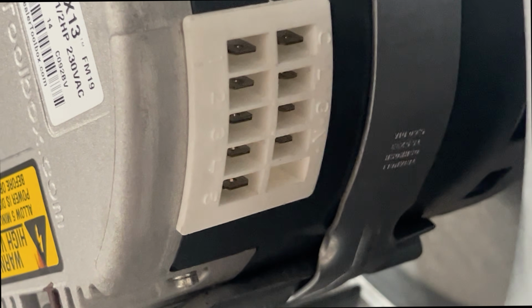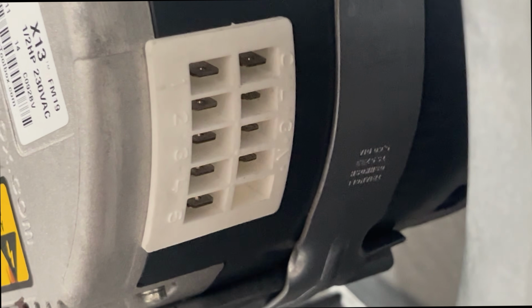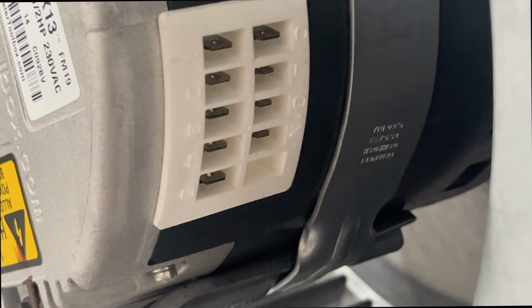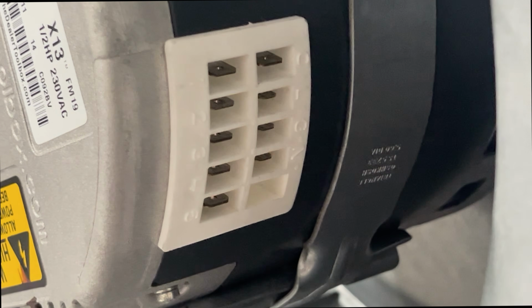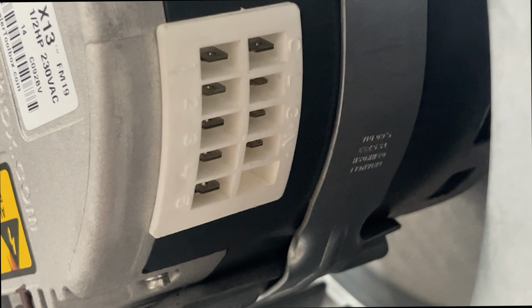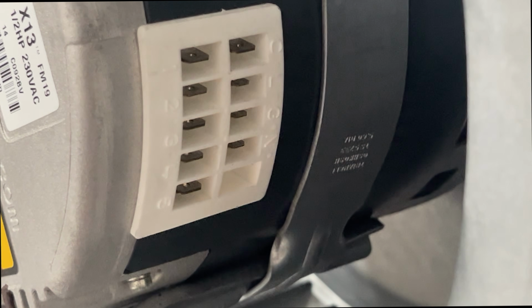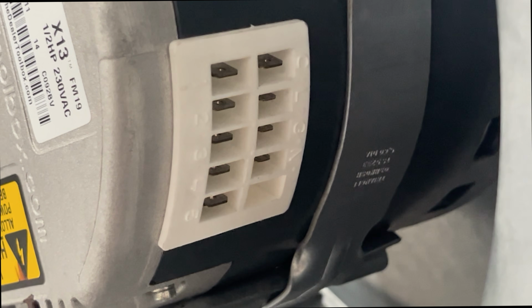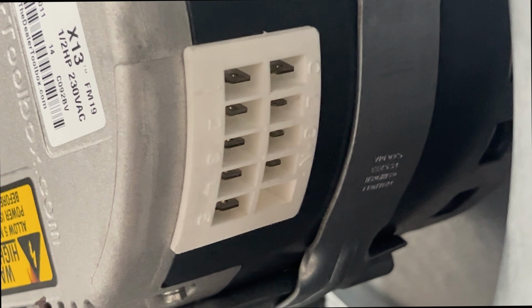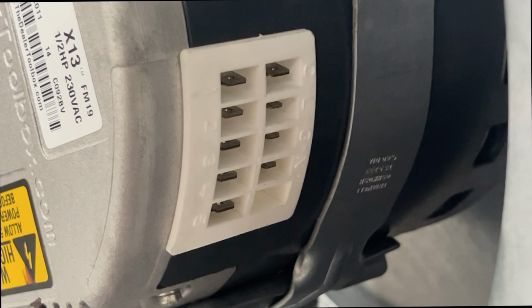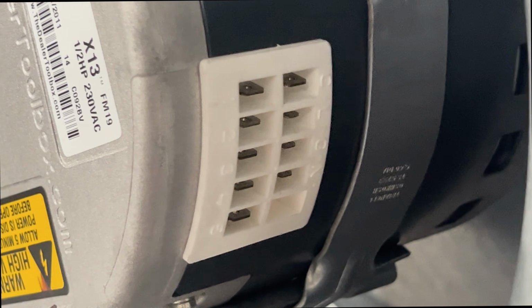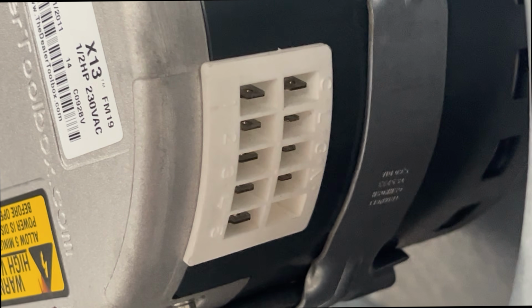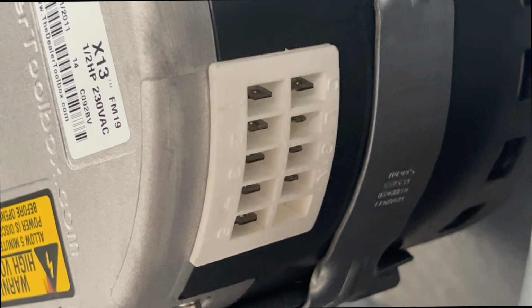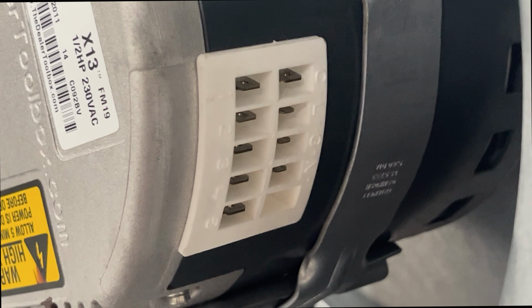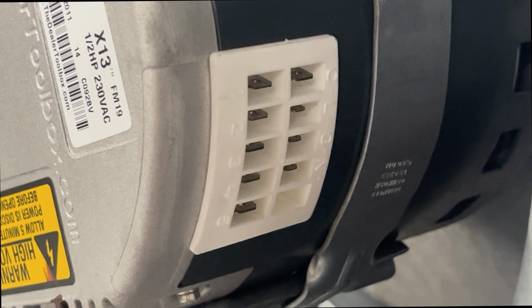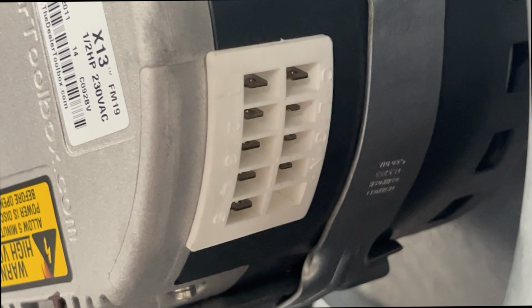I'm going to go ahead and blow it up a little bit, get a little closer in there so you can see I have on the back side C, L, G, N. So there's 4 terminals. On the front side, I have 5 terminals. That's 1, 2, 3, 4, and 5. Now, 1 through 5 are your different speed taps. So 1 will be low speed, 5 will be high speed, and 3 will be medium speed. So that makes 2 medium low and 4 medium high. And typically these come pre-wired for 2 and 4, which would be medium low and medium high. But you could put them wherever you need to.